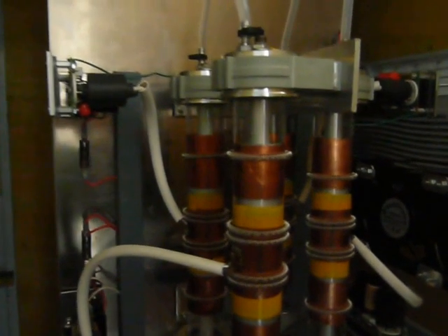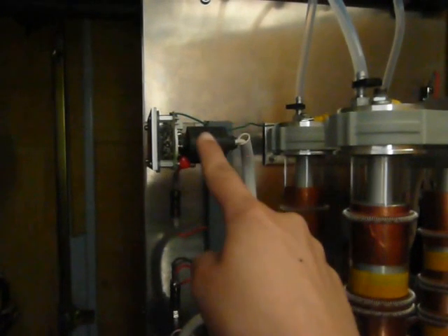Here we see that the ozone generator, this specific model is a 32HDHF, which produces 640 grams per hour from oxygen feed. What I'd like you to notice is that there exists an internal redundancy to the system. Here we have the corona lamps, and here we have the power supplies.